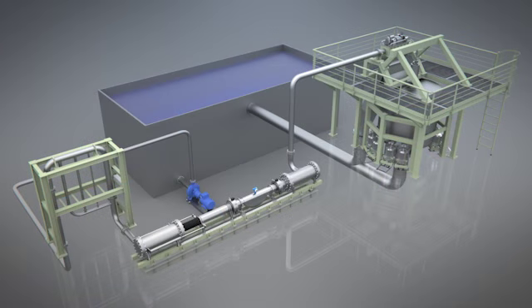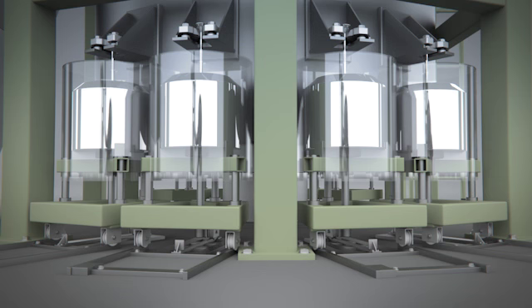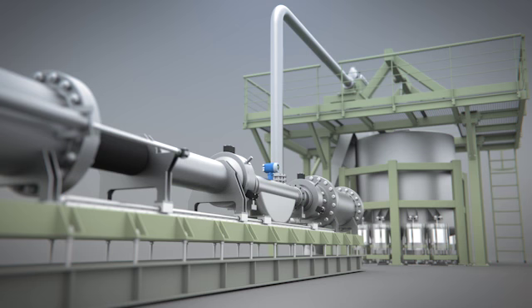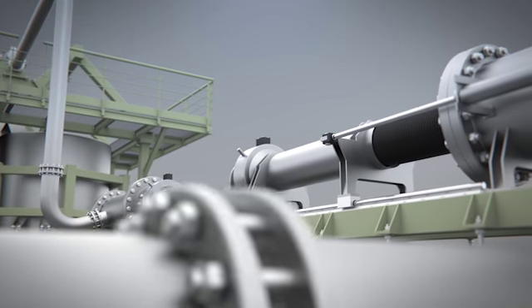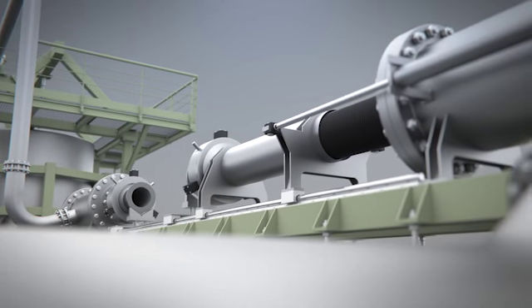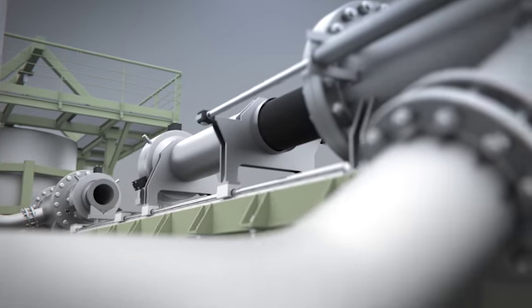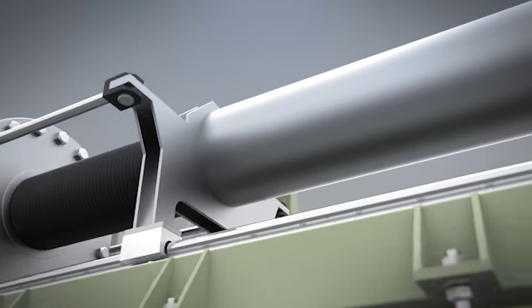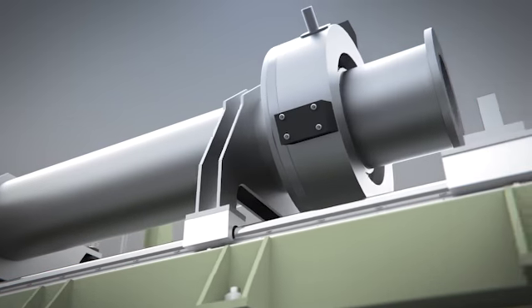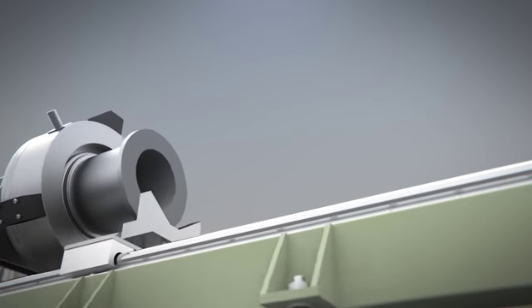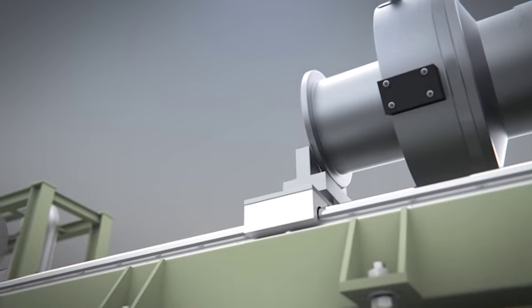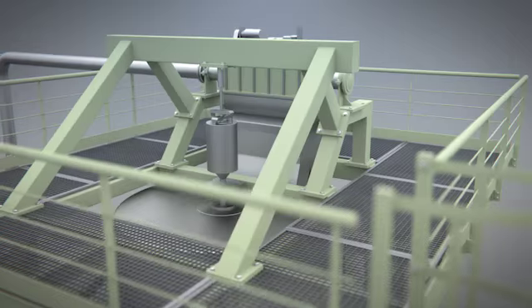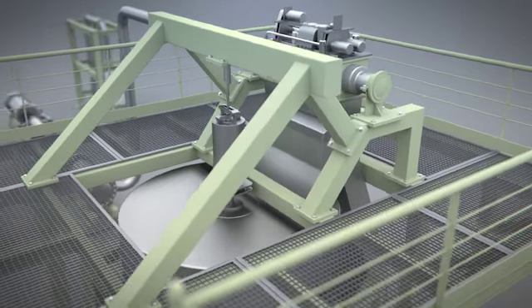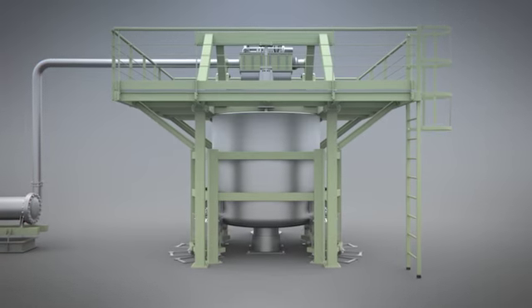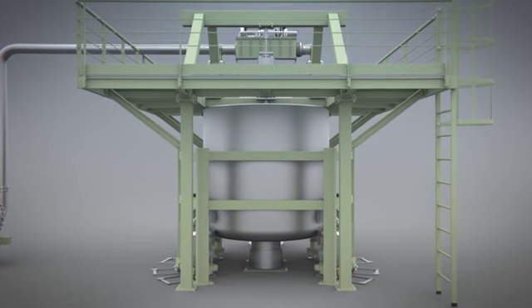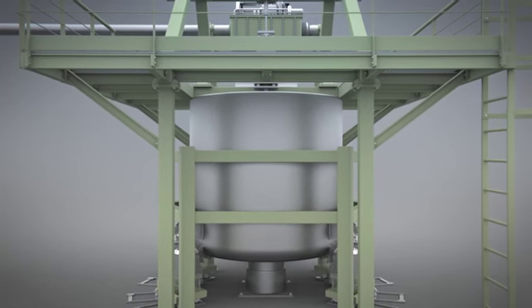For this purpose, Endress and Hauser operates highly accurate calibration facilities throughout the world. The accuracy of flow meters is of decisive importance, both in business transactions and for industrial applications. For this reason, Endress and Hauser has been building state-of-the-art calibration facilities for a long time to prove the accuracy of its own instruments flawlessly and traceably. These facilities apply highly precise measuring methods favoring calibration based on the gravimetric method.